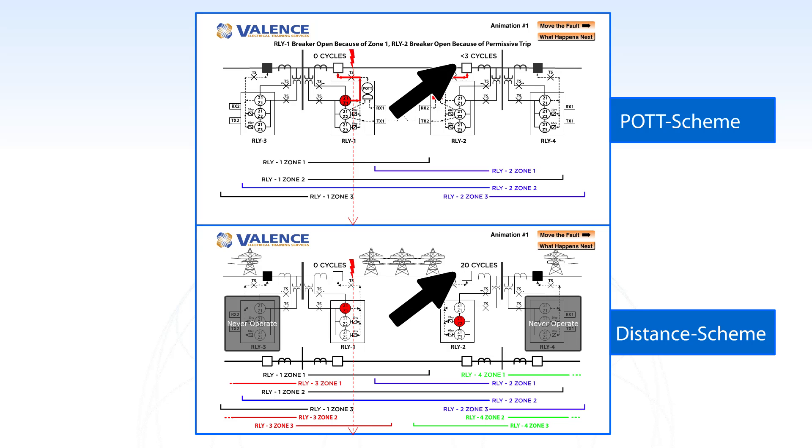All of the communication equipment, extra settings, and extra time necessary to install, set, and test a communication assisted trip scheme is used to reduce the amount of time a fault stays on the electrical grid by about 17 cycles. This may not seem like a big deal, but 17 cycles seems like forever in electrical terms.